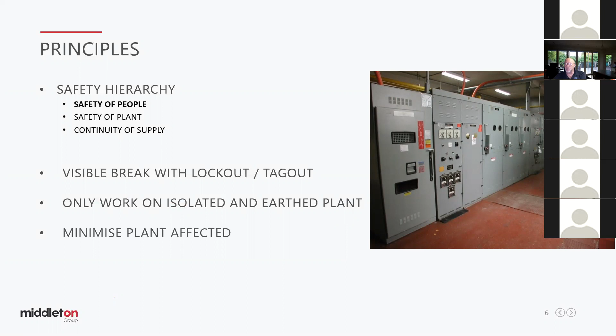So the basic steps for switching for isolation are: plan your switching steps, do your switching after you've got authority, apply isolations with lockouts, prove dead the equipment, then earth or short circuit, depending on the circumstance or the terms used, then issue your permits. So we'll now go through those steps and discuss how they work.